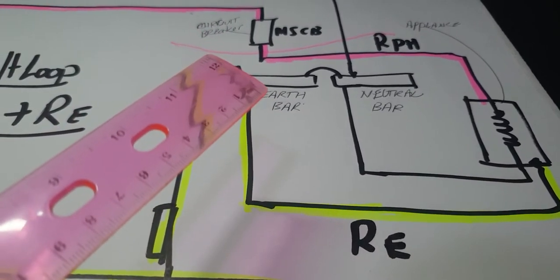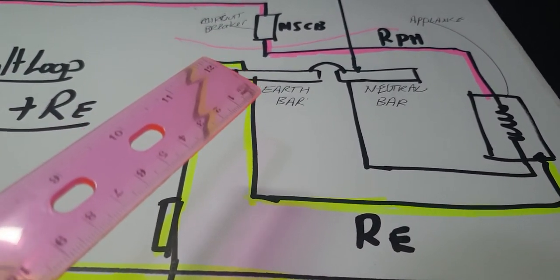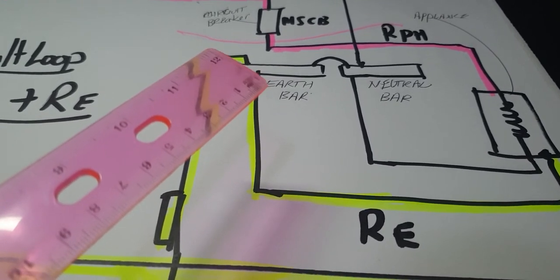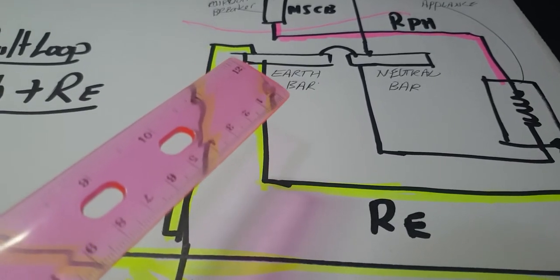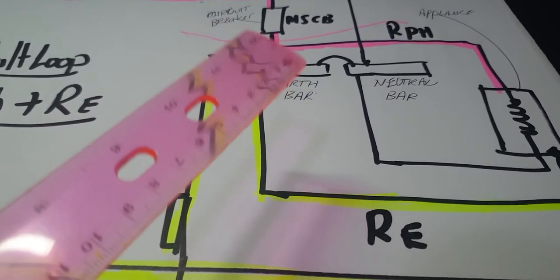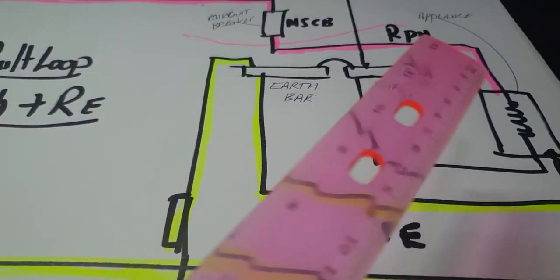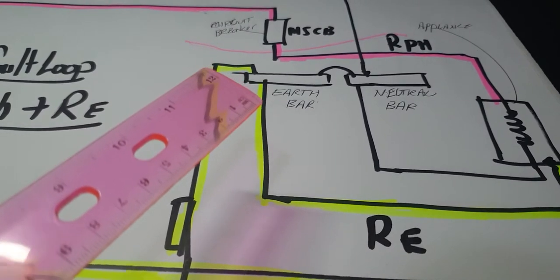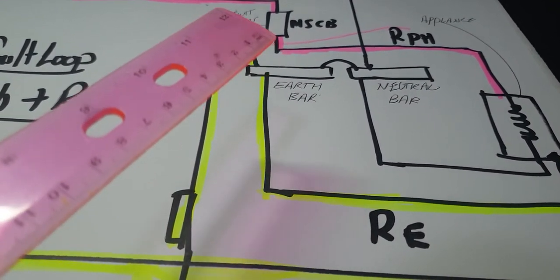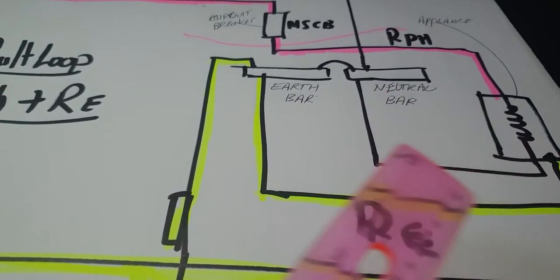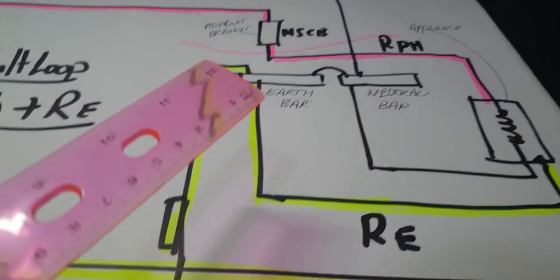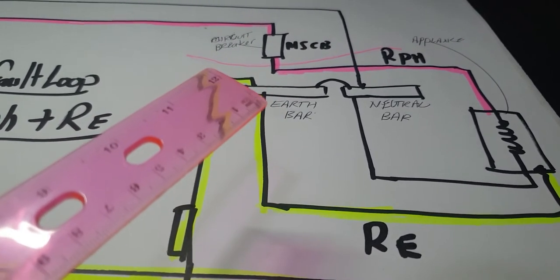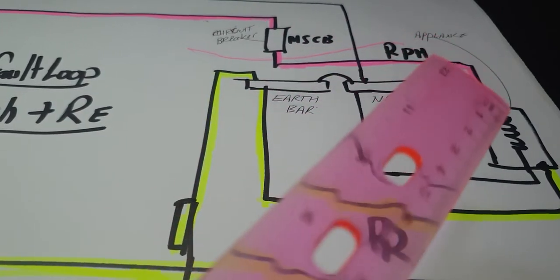That's why we work out the fault loop impedance here. That does change with breakers depending if I got a type B, type C, or type D breaker. On a type D, I've got to have 12 and a half times, where a type B it's only four times. There's a table called 8.1 and 8.2. 8.1 is for a live circuit, 8.2 is for a dead circuit, and that talks about the resistance of the active and the resistance of the earth on those tables.